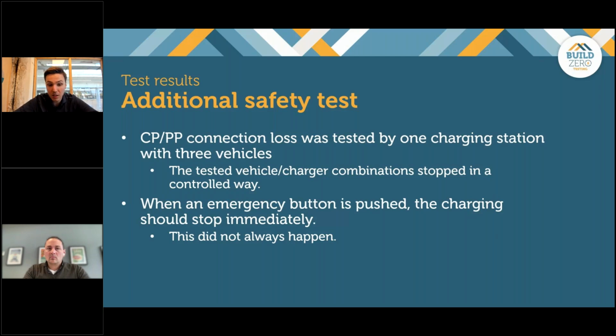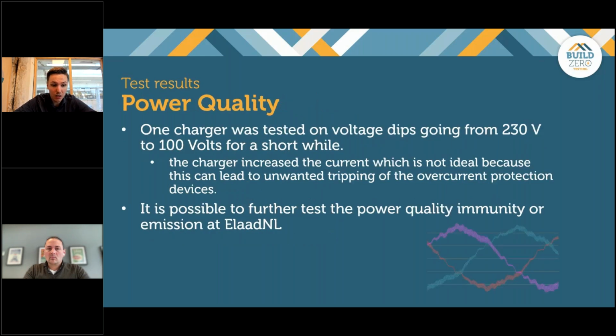I also mentioned Elaad participated in the test. We did all kinds of different tests, but also power quality testing. One test we did was a voltage dip. Normally the grid is 230 volts, and we created a short voltage dip to 100 volts, which can happen in the grid when, for example, there's a short circuit somewhere else.